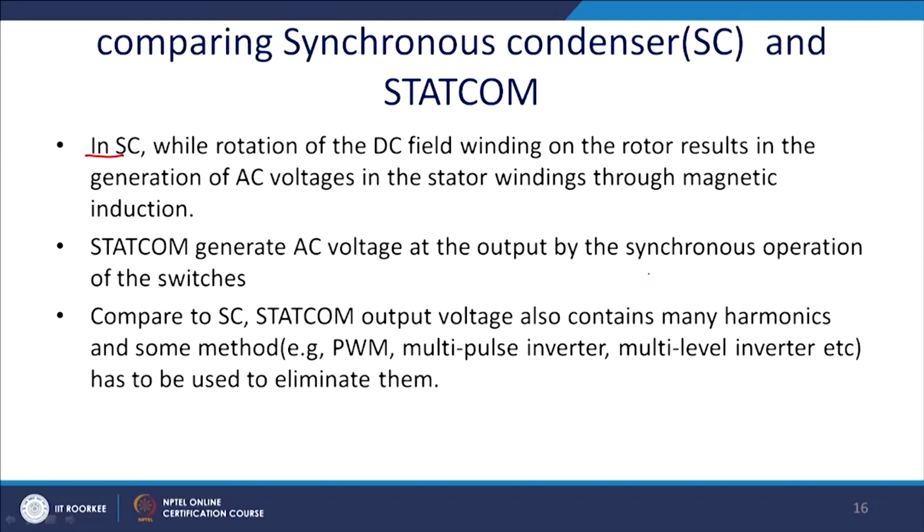Compared to SC, the Statcom output voltage also contains many harmonics. There are mainly switching harmonics, but please understand that the power system is a low pass filter, so the switching harmonics will automatically mitigate, or you can put in a low pass filter.